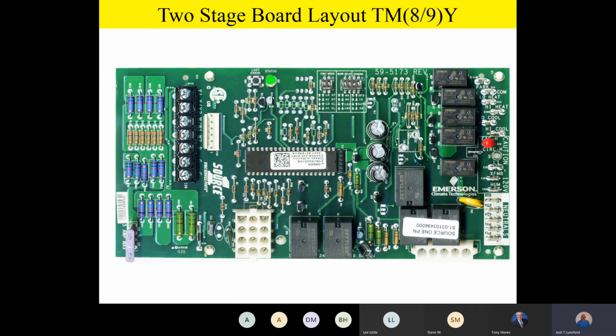So the one thing they like about our board, it seems like a lot, is I spend a fair amount of time talking about the staging of the board if you're stuck with a single stage thermostat. They seem to really like that a lot. But as far as the other stuff, it's pretty straightforward. The other thing they really like is the fact that we build in a flame current pad, so they don't have to have a special meter now to read flame current on their service calls.